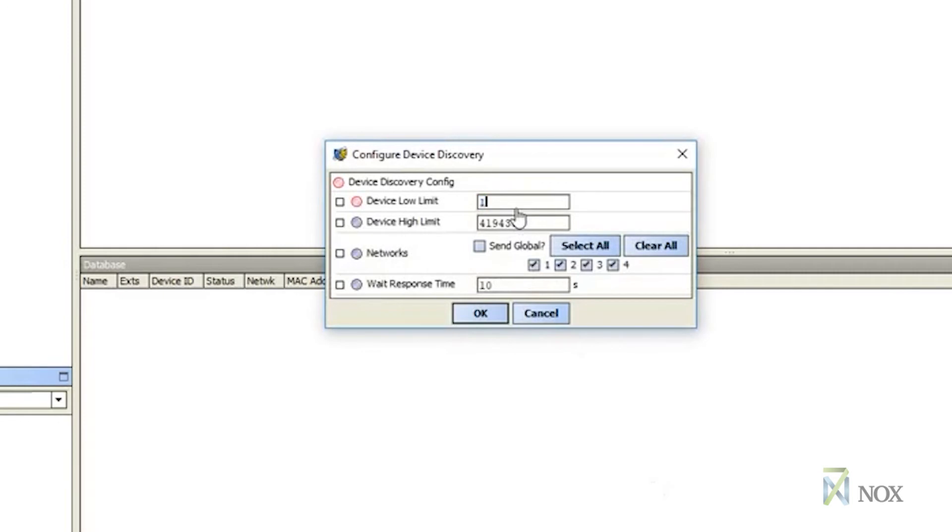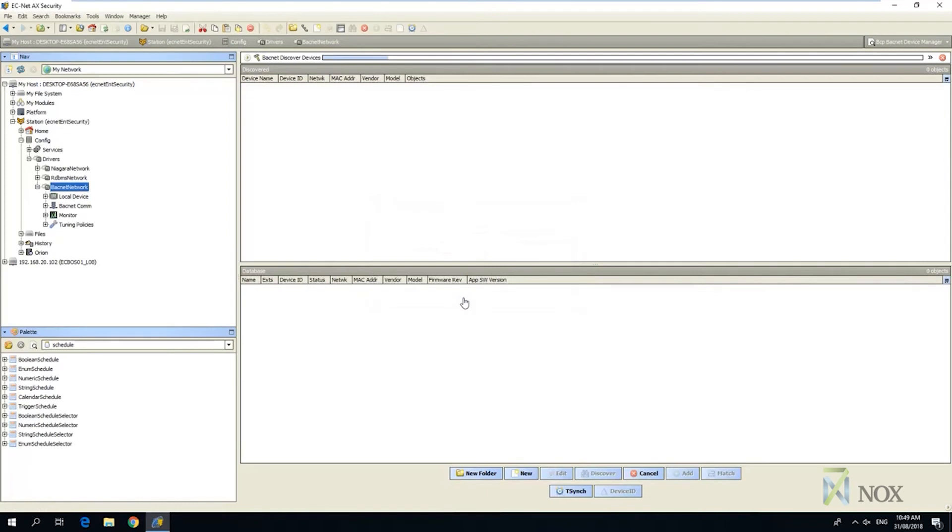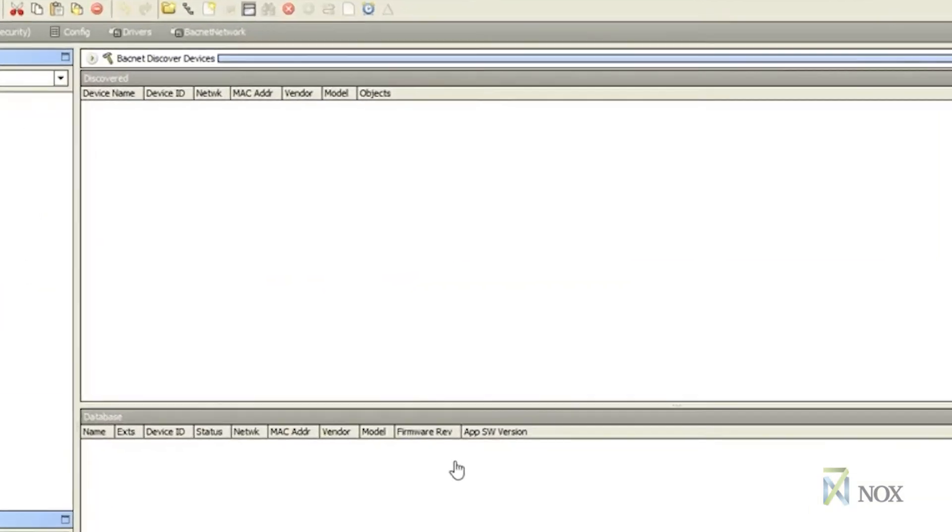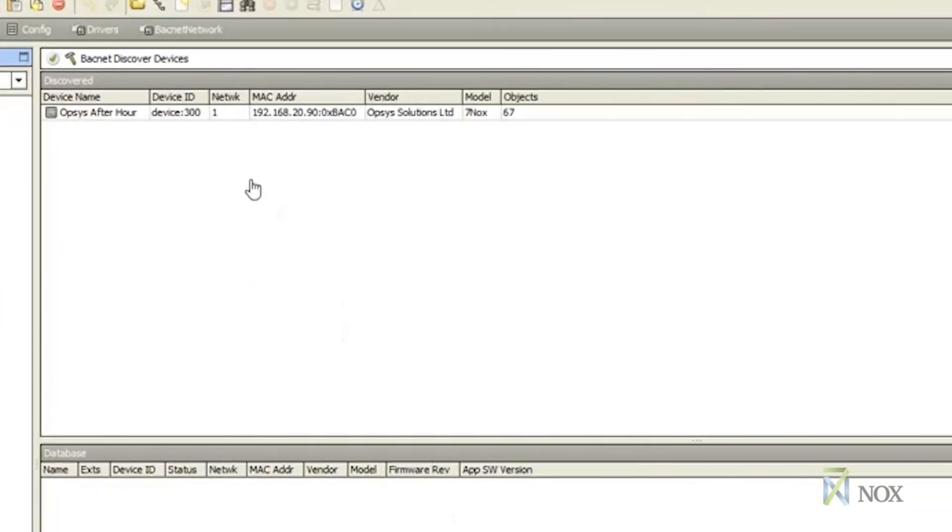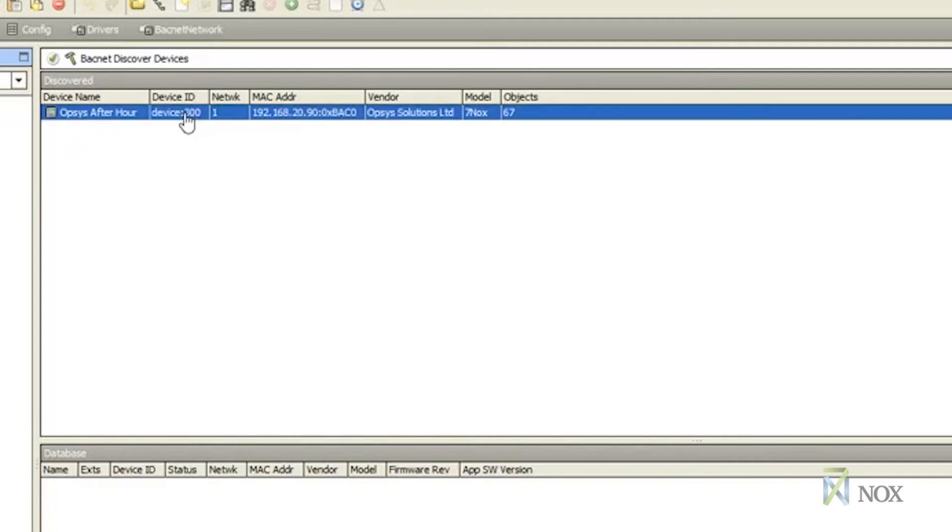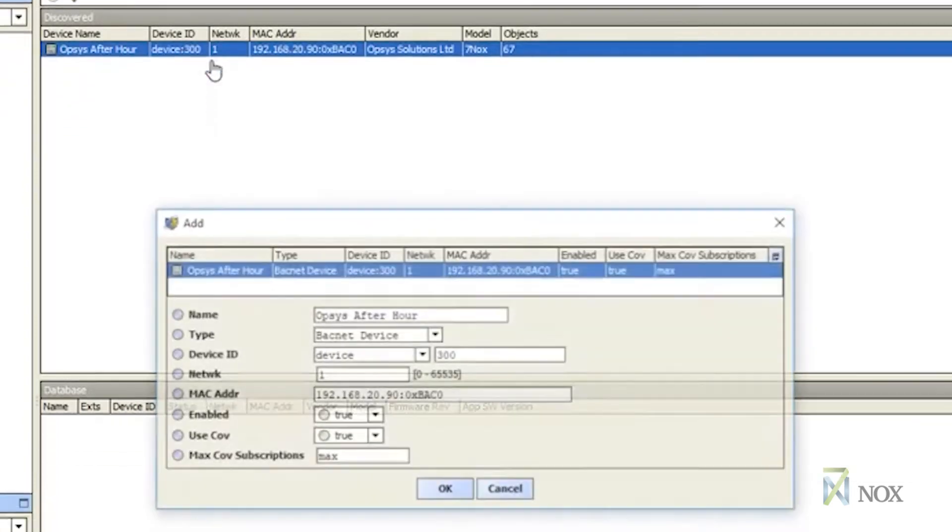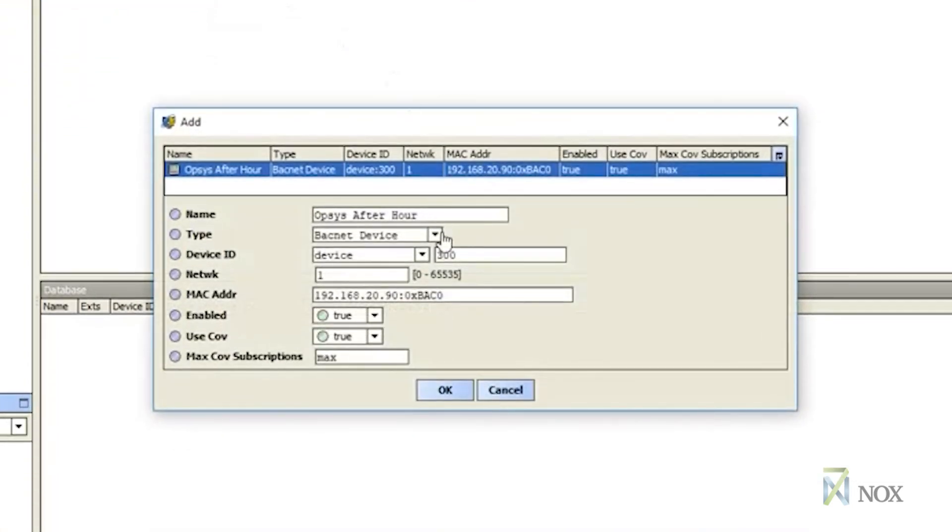Configure the device discovery, device low limit and high limit, and press OK to continue. Please note the device high and low limit will depend on what the site device has been configured to, which will vary from site to site. Once the discovery has finished, you will see the Opsys After Hours device appear in the Discover Devices window. Select the device and add.